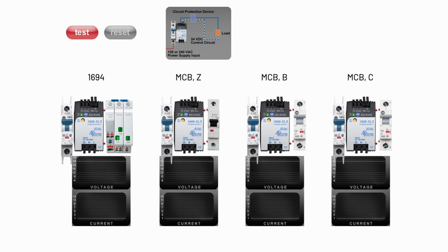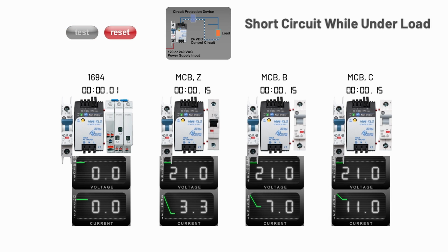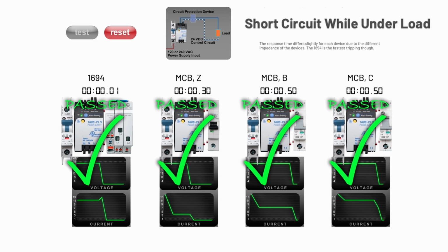The next example is very interesting, and it simulates a short circuit under load while current is actually running through the circuit. As you can see, all of the devices passed the test and tripped in a reasonable amount of time. However, the 1694 tripped much faster and therefore had the best performance.